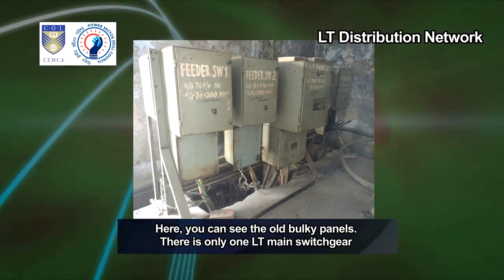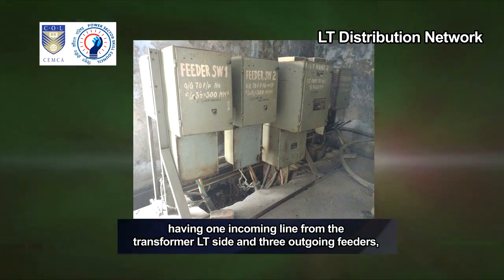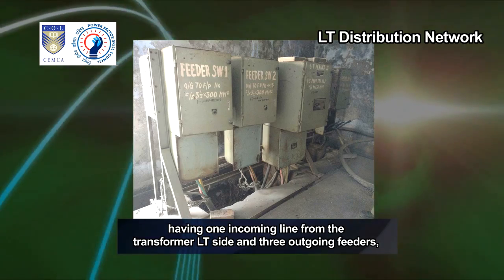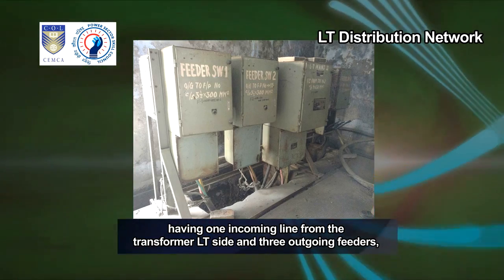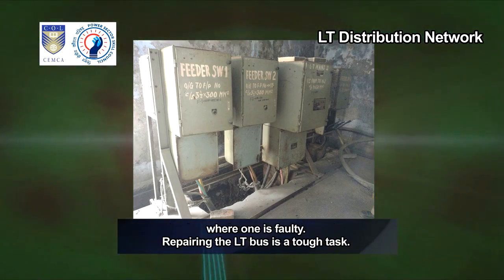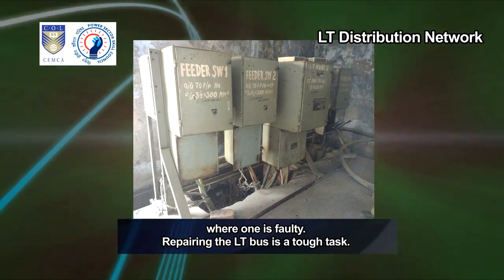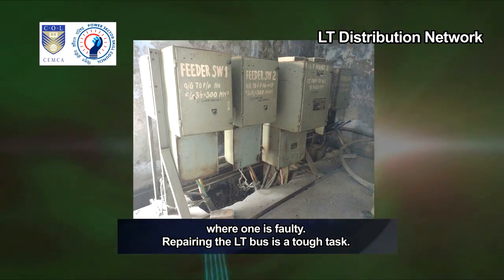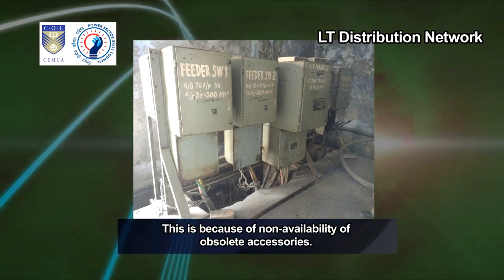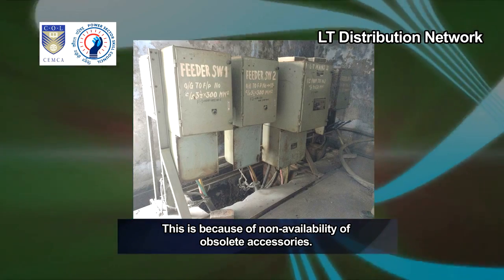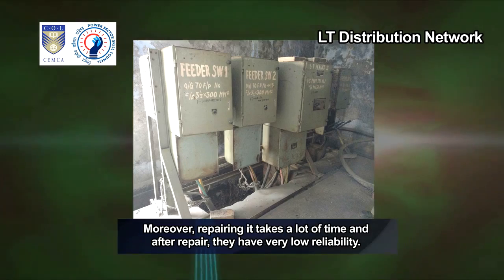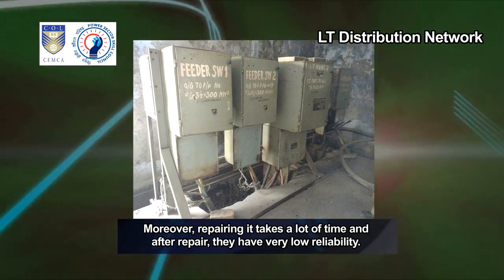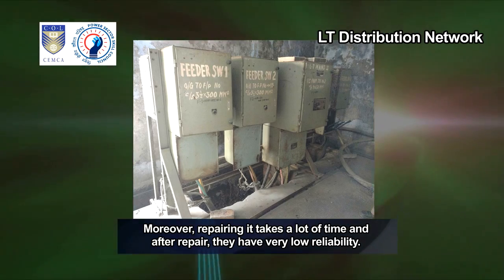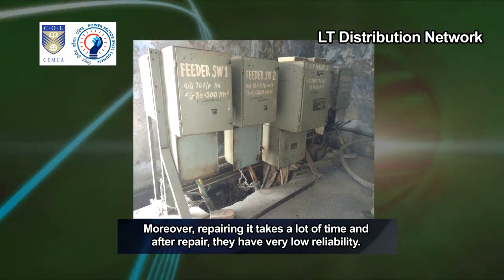There is only one LT main switchgear having one incoming line from the transformer LT side and 3 outgoing feeders, where one is faulty. Repairing the LT bus is a tough task. This is because of non-availability of obsolete accessories. Moreover, repairing it takes a lot of time, and after repair, they have very low reliability.